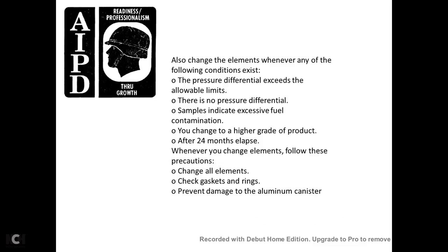Also change the element whenever the following conditions exist: the pressure differential exceeds the allowable limits; there is no pressure differential; a sample indicates excessive fuel contamination; or you change to a higher grade of product; or after 24 months have elapsed. Whenever you change an element, follow these precautions: change all the elements, and check the gasket rings.